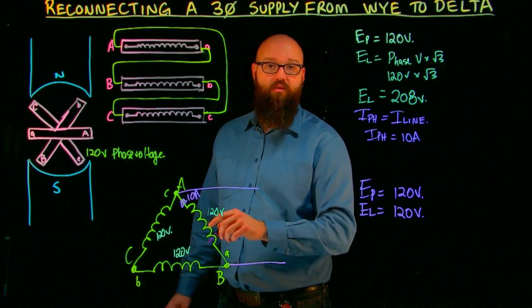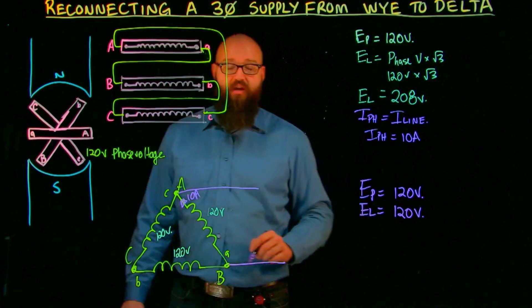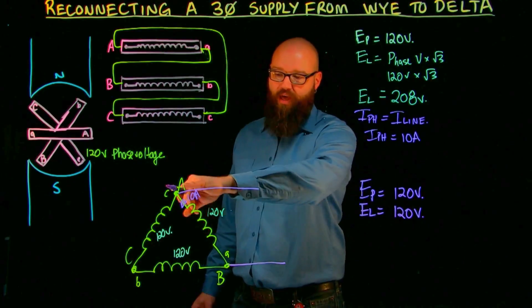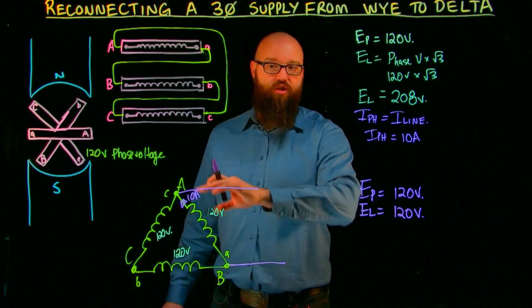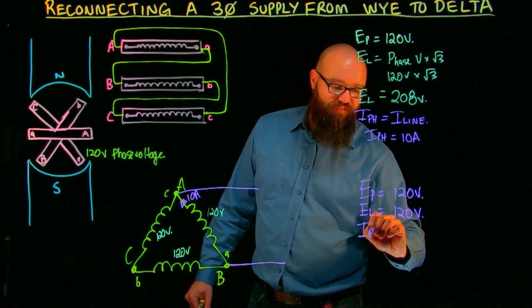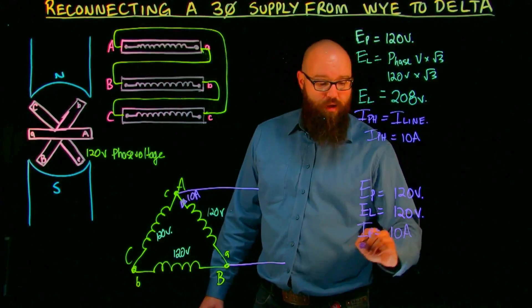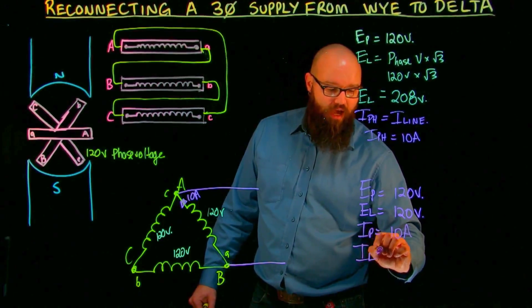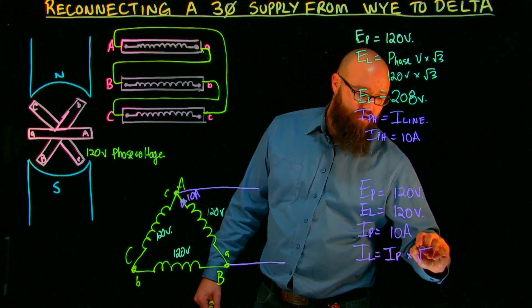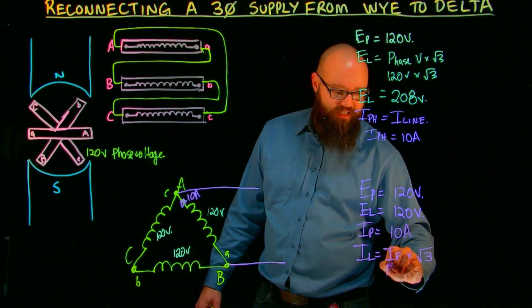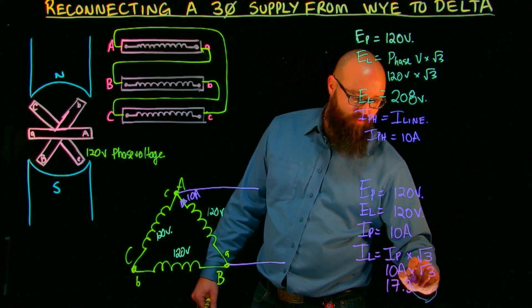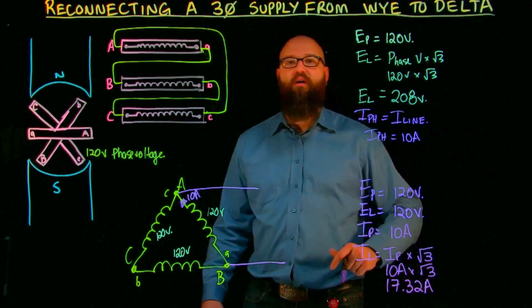So the next thing we're going to take a look at is current. I have 10 amps on my A phase. And we know that line current in a delta is made up of, for example, A to B plus A to C, not just the 10 amps of phase current anymore. So we have I of the phase is equal to 10 amps. But now I line is in a balanced system, I phase times root three, or in this case, 10 amps times root three, which means we now have 17.32 amps of line current.